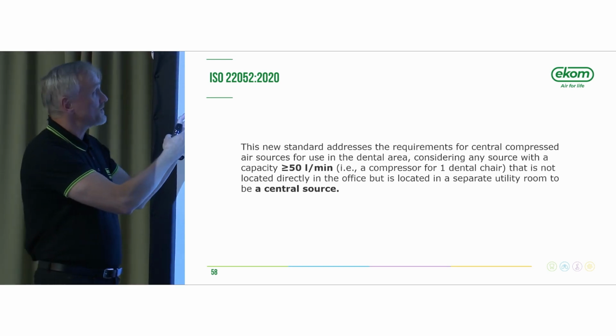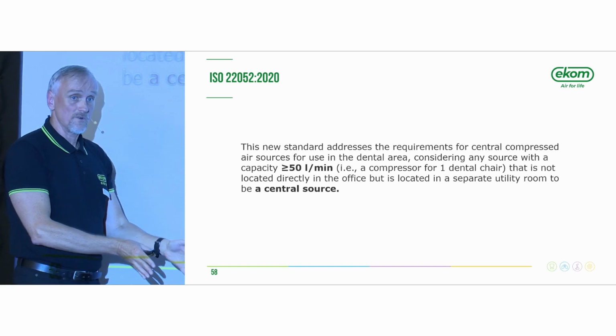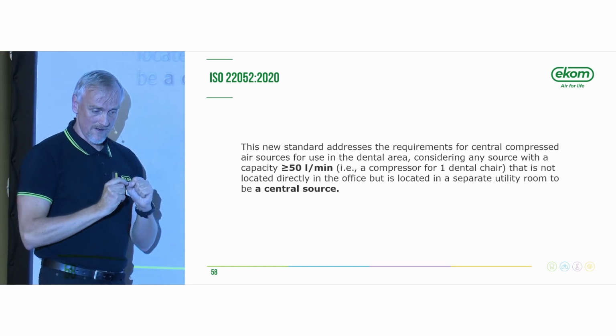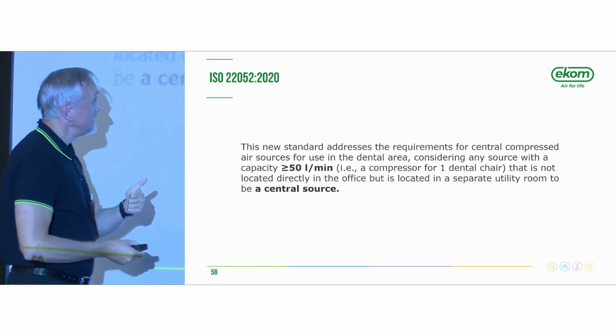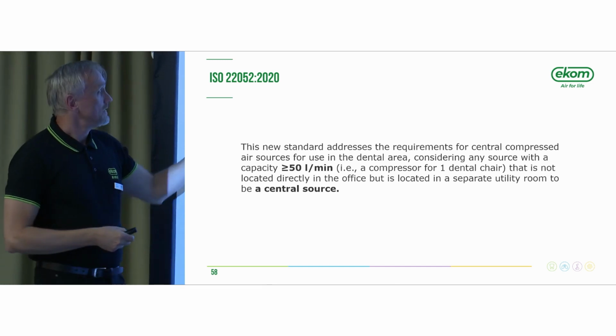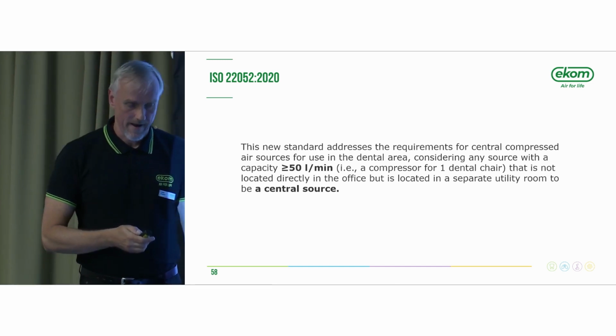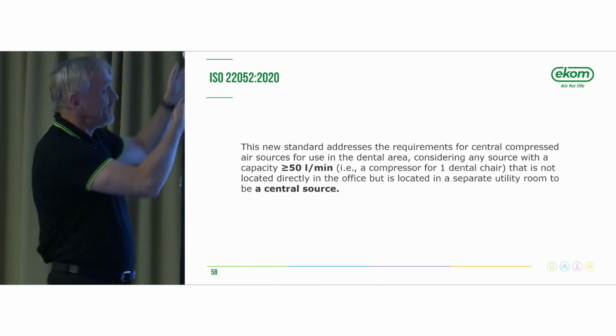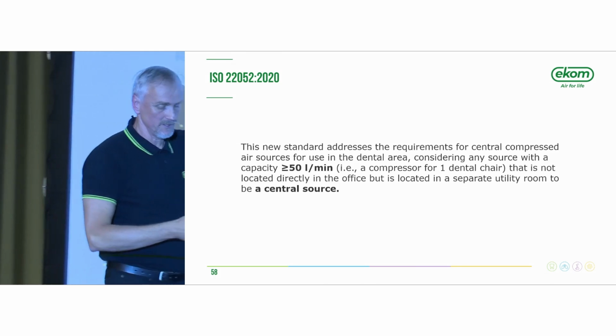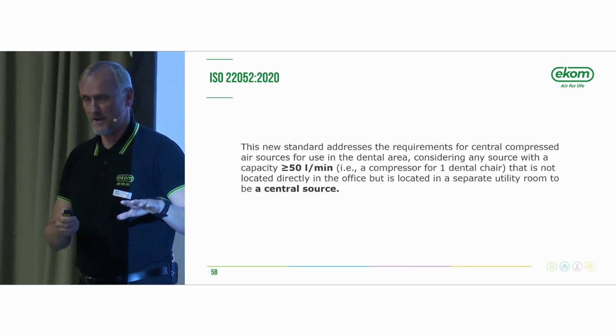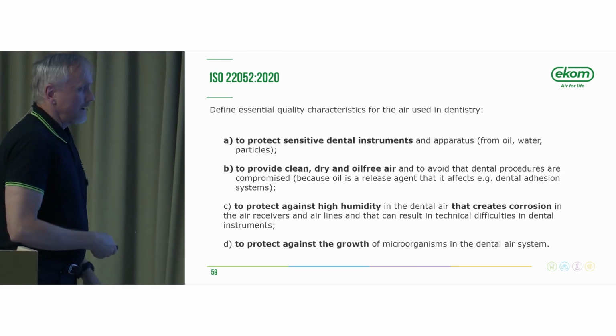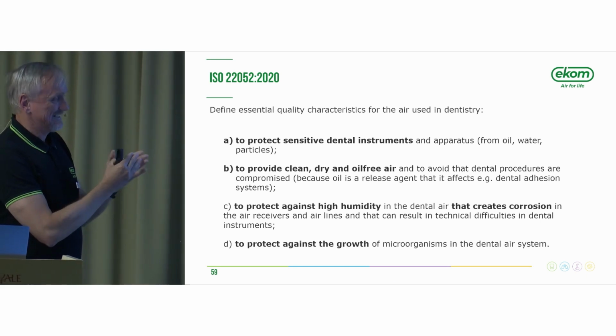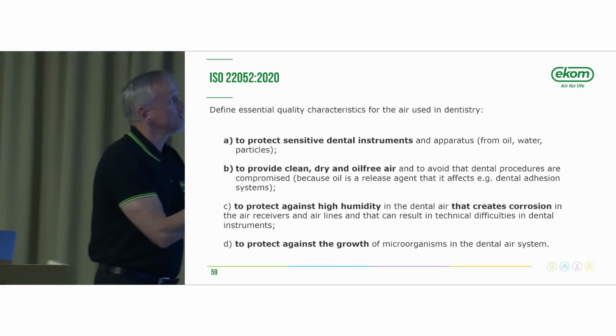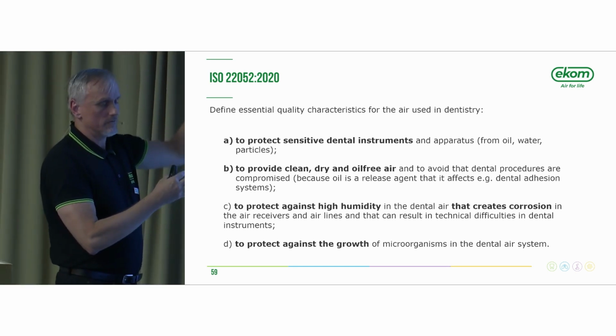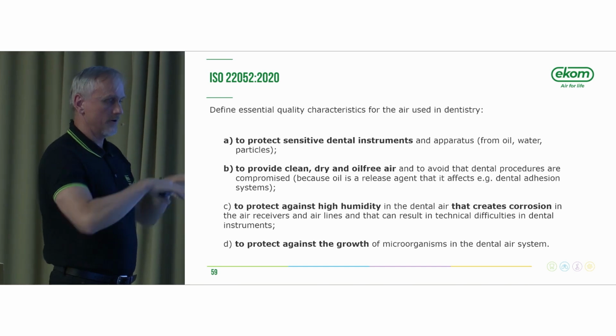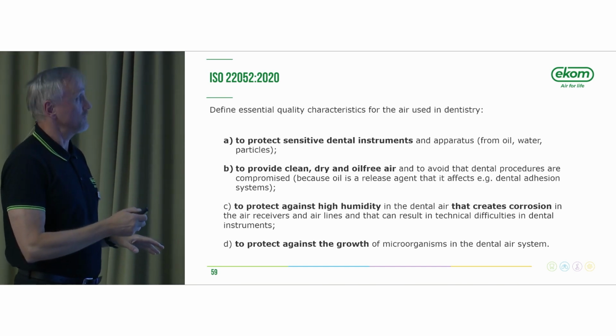According to this standard, even the smallest compressor, from our perspective, which is for one dental chair, is considered a central source of compressed air—of course, only if it's located in a separate room, not in the patient room. Here are the reasons why this standard is recommended to members of the European Union.